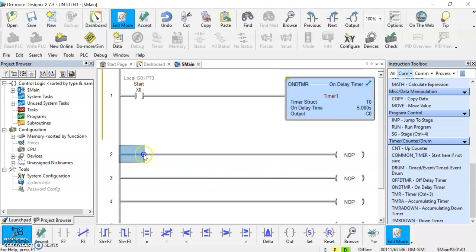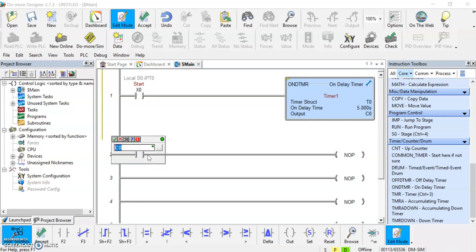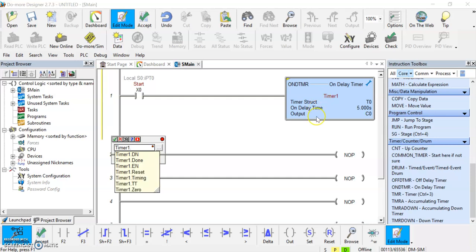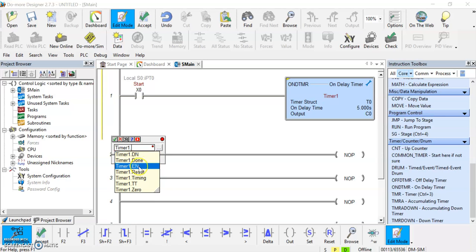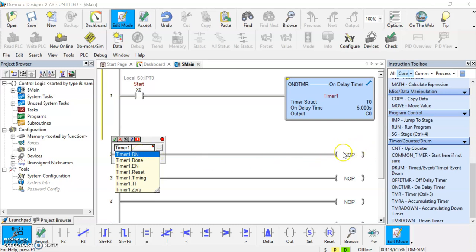So now what I'll do is I'll go into rung 2 and I'll put another normally open contact in there. F2. And I'm going to call that. I don't have to call it. It's already named because it's going to be associated with this. So if I start typing in timer 1 and I hit dot, then I have a bunch of different functionality that is going to be associated with that. Now DN and done are the exact same thing. What DN is just Allen Bradley speak. So that's just what they've incorporated into this. The EN is when the timer is enabled. So when this rung goes true, and I've only got one instruction ahead of it. So when this goes true, this timer is going to be enabled. And this bit down here will go true. And if I have something associated here, then that would also be operated.